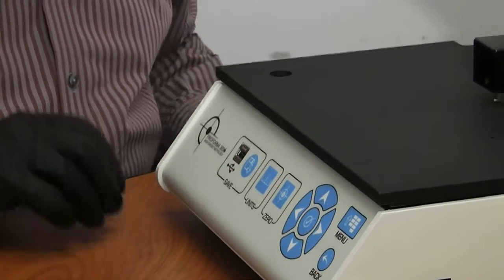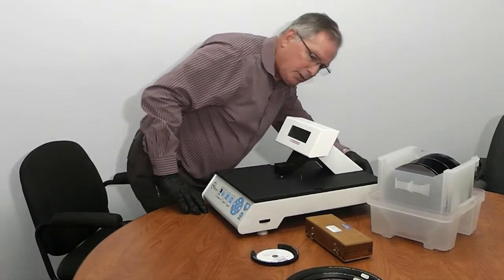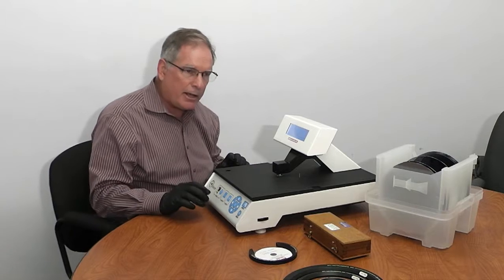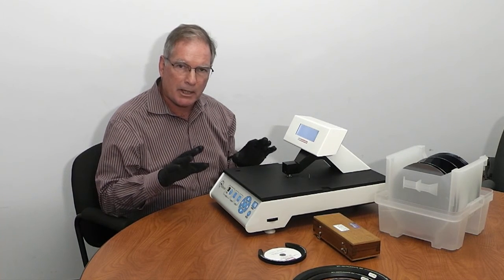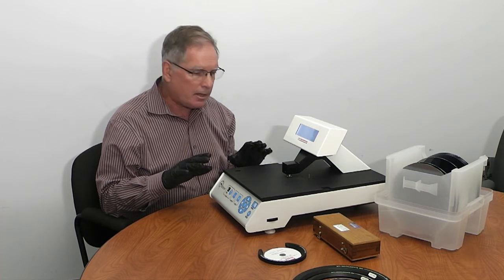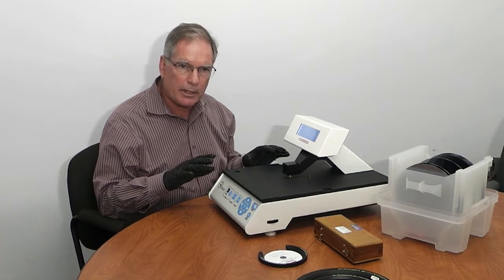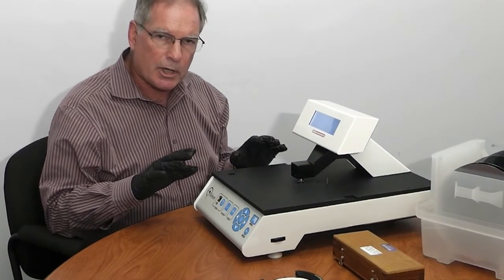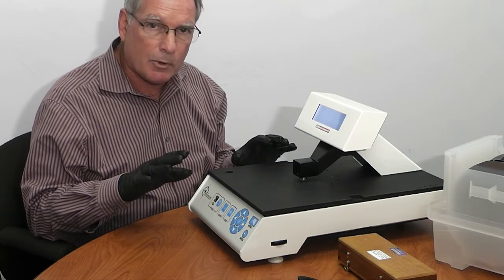Next thing we're going to do is turn the instrument on and let it warm up. In order to get good, stable readings, you want to let this instrument warm up for about 30 minutes. The amplifiers need to thermally stabilize inside. We do have a little fan for cooling, but for the best results, always turn this on 30 minutes before you start your readings. It's okay to leave it on all the time, also.